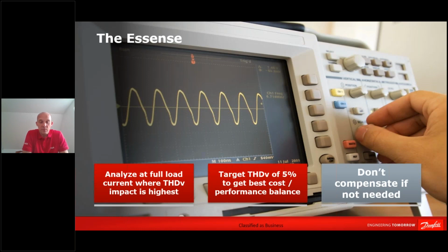Whenever you're using Danfoss drives, you don't need to do harmonic analysis when your sum of drive loading is less than 40% of your transformer size. So if you have a 1000 kVA transformer and you have 400 kilowatts of drive loading, then you don't need to do your analysis, because then you're always safe. Then you always have a voltage distortion level that is less than 5%. When you're applying 800 kilowatts of drive loading on a 1000 kVA transformer, that's where you need to do the analysis to see if you're good or not. So the 40% loading is normally what I advise customers and consultants to use, simply as a guiding star for when to do the analysis.